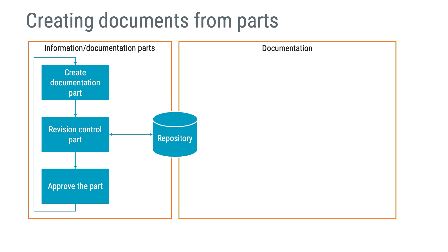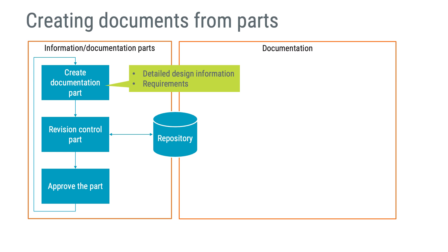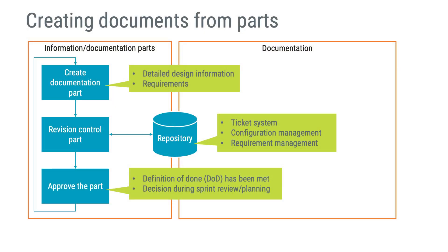The documentation parts can be stored as detailed design information in a ticket or as individual requirements in a requirement management system. The repository used to revision control the parts can be a ticket system, configuration management system, or requirement management system. The last step is approving the part — and this means the team approving the part, not necessarily using Part 11 compliant digital signatures. This approval can take place during a peer review of detailed design information in response to agreed criteria in the definition of done, or during a sprint review or planning.